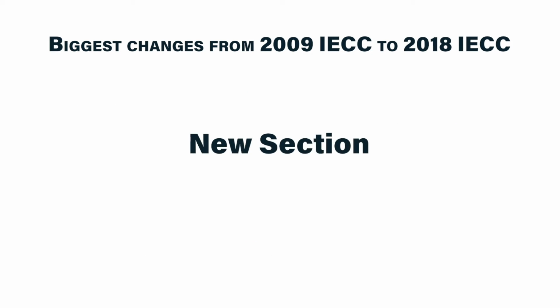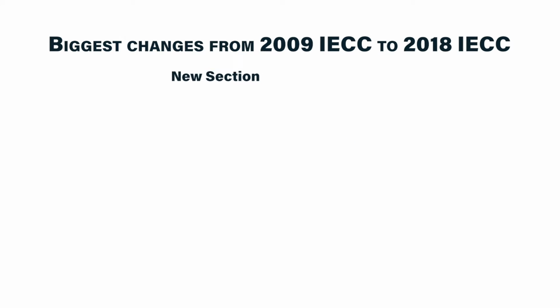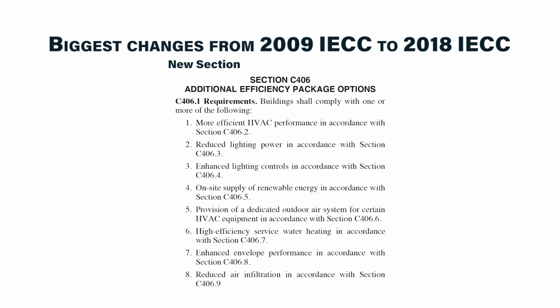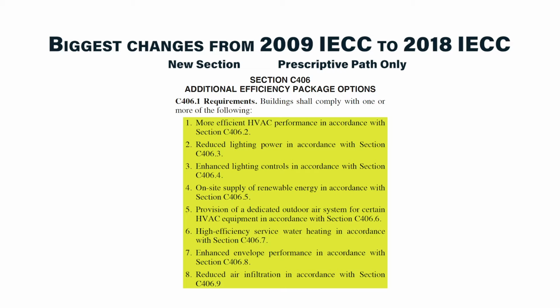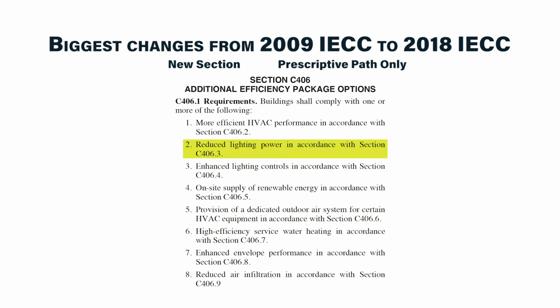There are also two new sections in IECC 2018. The first new section is Additional Efficiency Packages, which applies only to prescriptive path projects. These projects are now required to comply with at least one of the energy efficiency options under this section. For example, if the reduced lighting power option is chosen, a project will need to reduce its interior lighting power by 10% or more than the base allowance.